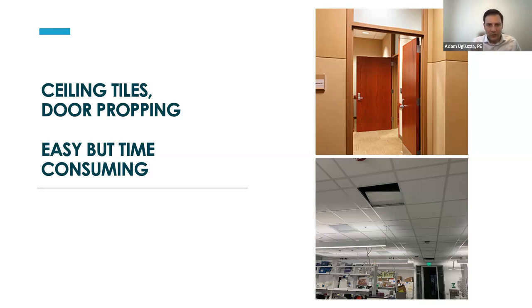Propping interior doors is another one. Just an example of that up top, making sure those doors are open allows communication. We're basically pressurizing the building from one, two, maybe three locations, not like the HVAC system that has ductwork that goes everywhere. The way we communicate air is through hallways and doorways, to get the entire building pressurized uniformly.